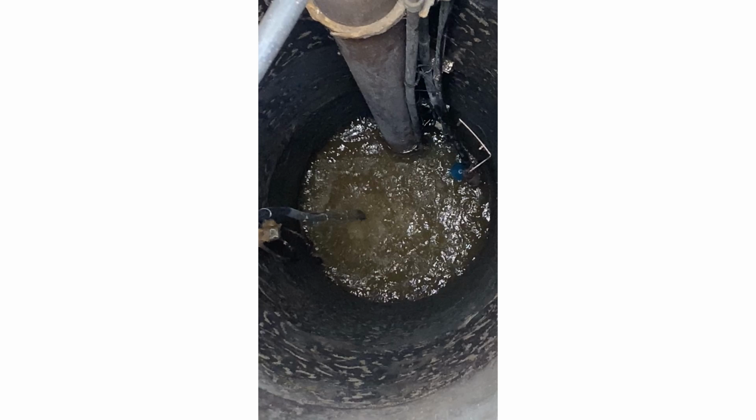Okay, and that concludes this presentation on fog control using aeration. Some side notes would be that while I say continuous aeration for a week or a month or whatever in these videos, that is true, but because we want to prevent cavitation as much as possible, and cavitation being when a pump sucks in air bubbles or creates micro air bubbles while running, every time the pumps turn on to suck in and pump water out of the wet well, we have the aerator set to automatically turn off once the pumps come on.